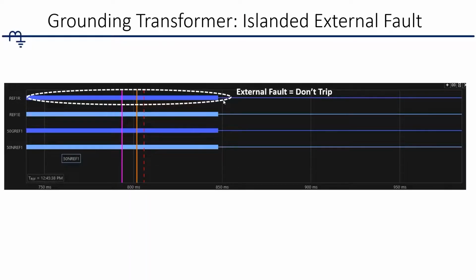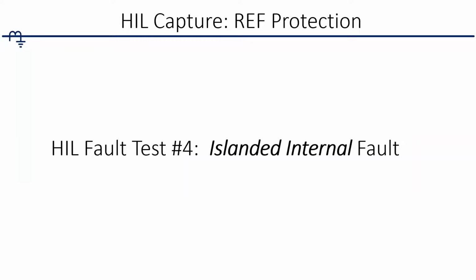So the relaying at this point says, okay, yep, external fault. I'm not going to trip. And we did this several times. We slid the fault throughout the network and got the same result every single time. Which is good. That means it's correctly identifying external versus internal faults, grid tied and grid isolated.